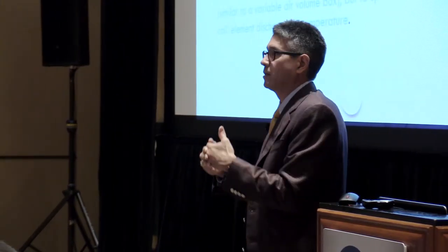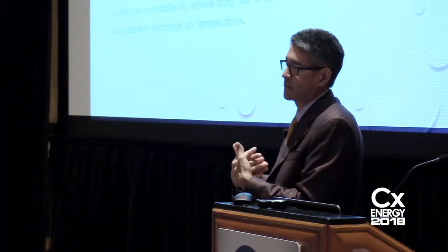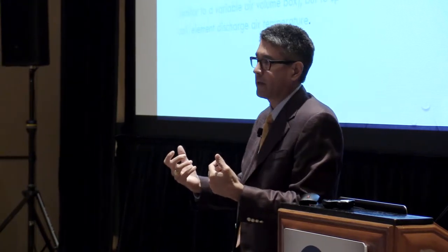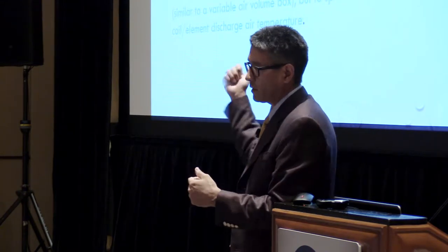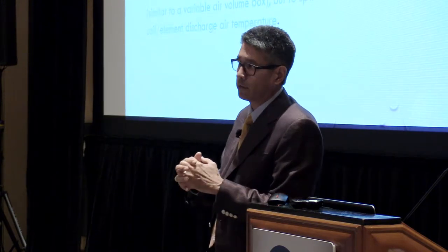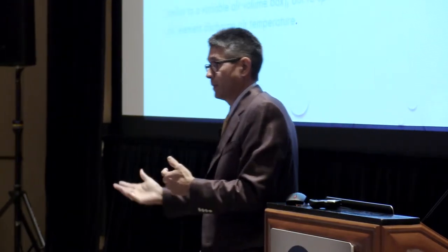So that's where you start looking and say, do I really have a pressure independent system just because my pump is controlling to a differential pressure set point? You got to look at your load and say, what's happening at my load? And how are my controls controlling that valve to make it pressure independent? A VAV box is controlling to an airflow set point. Control valves in most situations are typically not controlling to a water flow. Typically, they're controlling to what? Discharge air temperature or room space temperature. They're not controlling to that water flow.